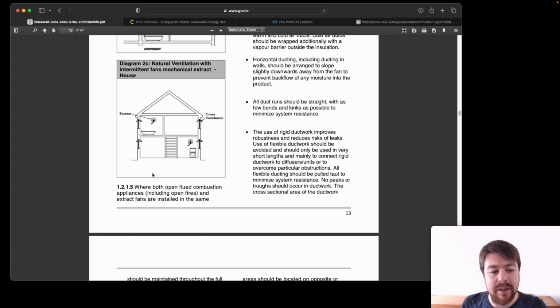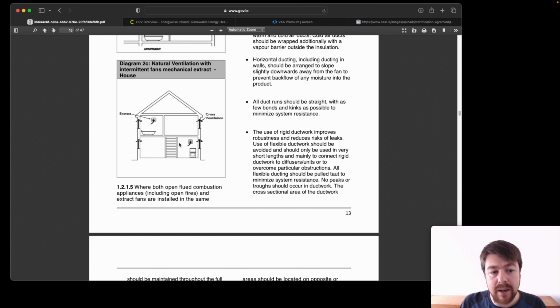What typically happens in an Irish home, as you can see in diagram 2C, is cross ventilation, where you have ventilators — essentially holes in the wall or window of an engineered size — and air just blows in and out. This is called natural or passive ventilation. It's simple to achieve and effective, but it has drawbacks: you waste a lot of heat because you have no real control over what goes in and out, and in some cases it's inadequate because users end up taping over joints, which doesn't work out well.